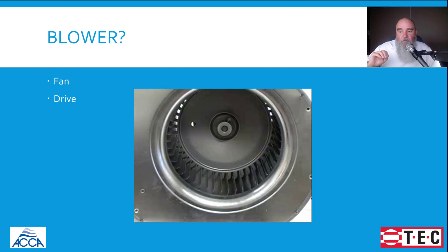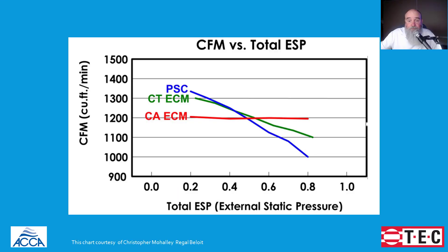I want to stick to some basic information in this video and cover some rules of thumb, some misnomers, or maybe a little bit of both. First, we're going to talk about what kinds of blowers or drives are available to us. Modern furnaces, modern air handlers: we have the standard induction motors, permanent split capacitor motors — they're in our rearview mirror, they're just not a thing anymore. The DOE made a rule change in the summer of 2019, and motors had to get more efficient. Luckily, we had ECM, or electronically commutated motor technology, available to us.